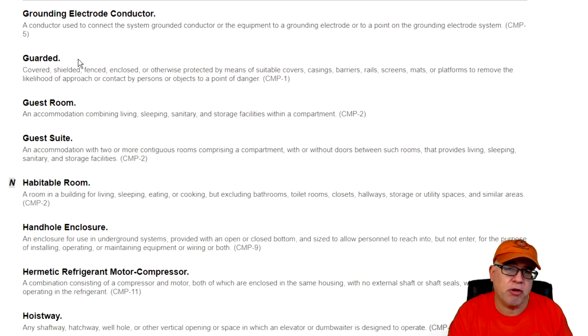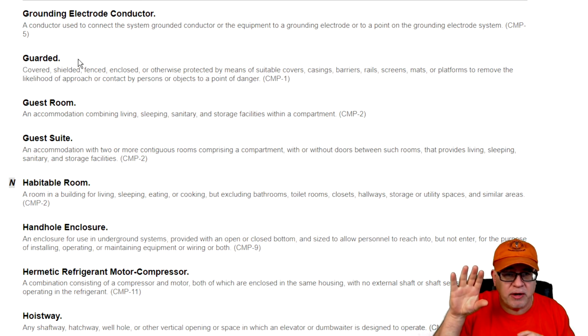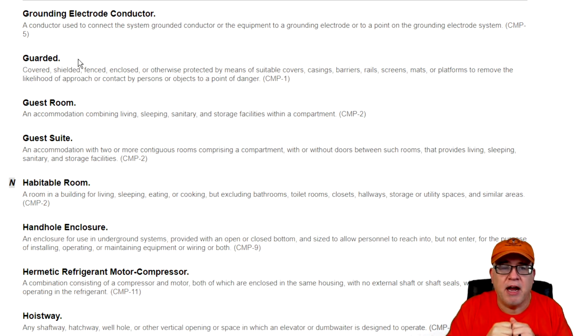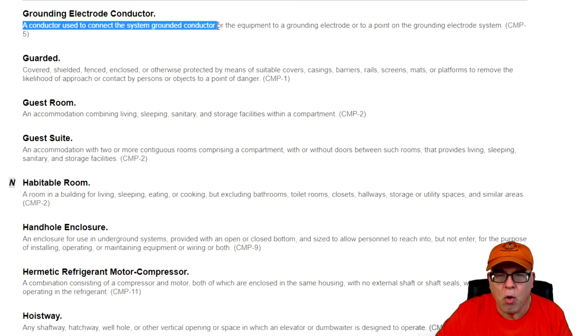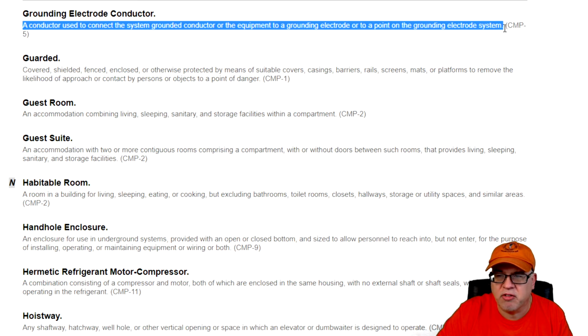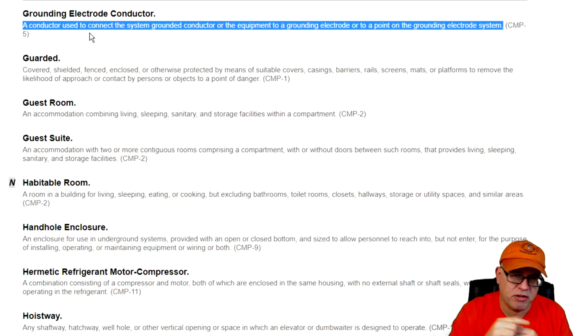Now, the connection from that electrode to the grounded conductor in the service, for example, or to the X0 point in a separately derived system, that is called a grounding electrode conductor. And we call that a GEC. That's our acronym we like to use. So it is a conductor that connects the system grounded neutral or the equipment to the grounding electrode or to a point on the grounding electrode system, okay? So again, a point on the system. So transformers, for example, that would be from that equipment, making a connection to the electrode, that's going to be a grounding electrode conductor, okay? From the grounding conductor in your service to the electrode, that's a grounding electrode conductor, okay? So those are examples where that connection is being made.